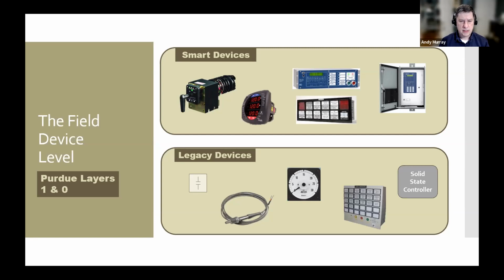These would probably be referred to in the Purdue model as level 0. Things like it could be a discrete contact. Oftentimes that's how we still get the status of a circuit breaker or a switch. The device would obviously have primary contacts that open up at that 115 kV level, and then there's a smaller low voltage contact that follows that would bring that status into SCADA.